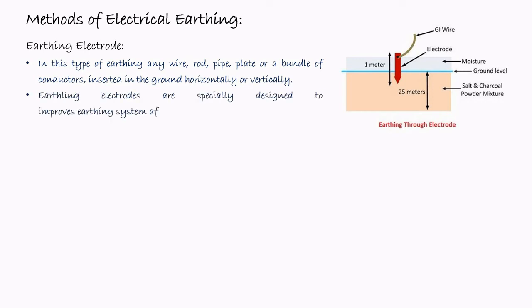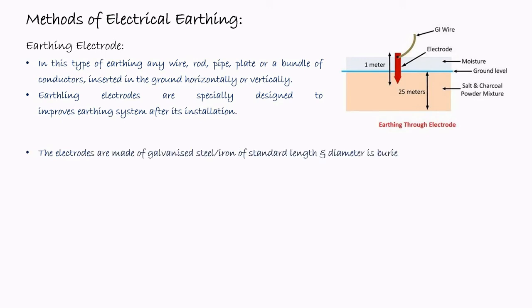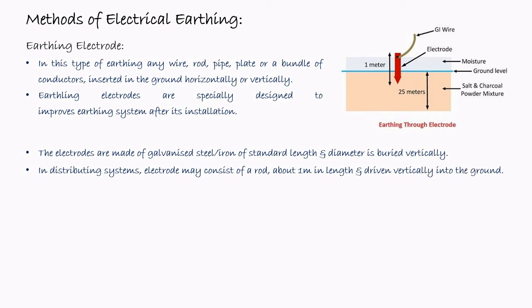The earthing electrodes are specially designed to improve the earthing system after its installation. Along with the other earthing systems, these earthing electrodes are also used to improve the overall system. The electrodes are made of galvanized steel or iron of standard length and diameter that is buried vertically. In a distribution system, an electrode may consist of a rod about 1 meter in length and driven vertically into the ground. That is shown here. The length of the electrode is around 1 meter and it is placed vertically into the ground.